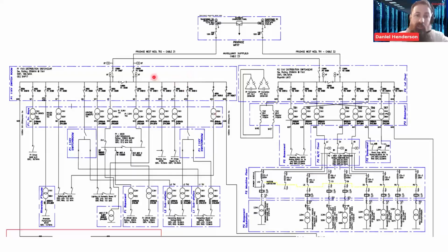What I will add to this is that we do have an interconnecting ring going from this 11 kV switchboard across to another 11 kV switchboard. So the original design would have had that as an open point, but there had been some recent power quality issues off-site. Up network, there were some overhead lines where they were getting debris impacting on the overhead lines, which was then causing power dips on the site. So this was closed, and it had been for a number of months, to reduce the impact on the network. So when you did have a dip upstream, you didn't have any impact downstream. The voltage ride through was suitable and sufficient then to not impact our network.